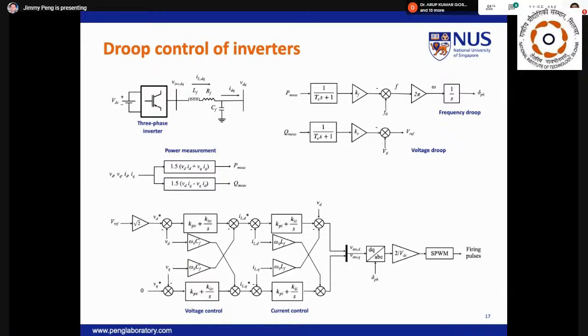The power measurements are computed from the voltage and current measurements in the DQ domain. Now, the Droop equations can be represented in the following control block diagram on the top. To make the Droop loop more robust to harmonics and high-frequency noise, measurements are passed through a first-order low-pass filter, as shown. The frequency of interest for Droop control is typically in the range of 2 to 10 Hz. To ensure adequate time-scale separation between the voltage Droop loop and the switching frequencies, the voltage Droop loop here defines the voltage reference that is used as the input to the outer control loops of the inverter. So they are reasonably well decoupled because of their different time constants.